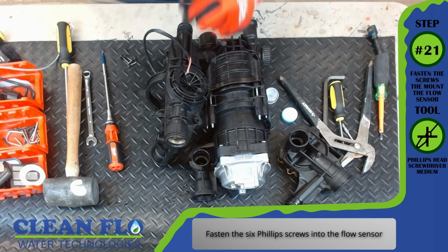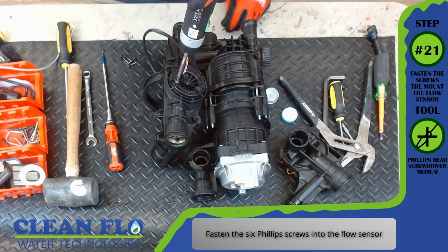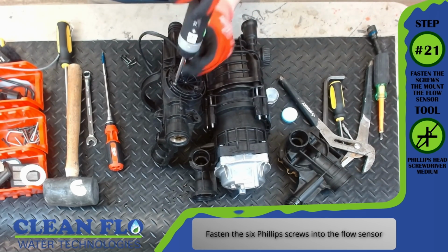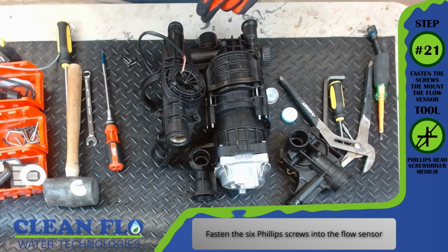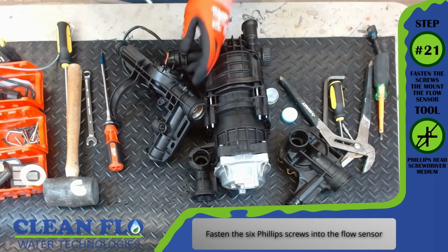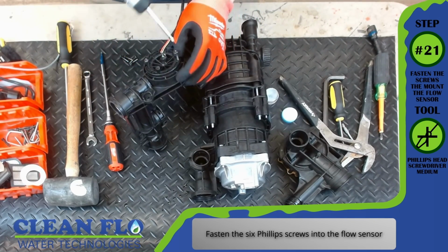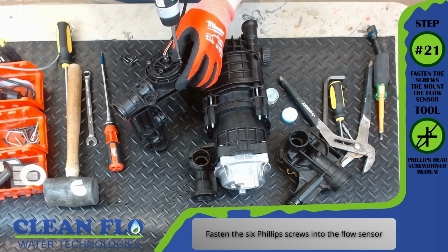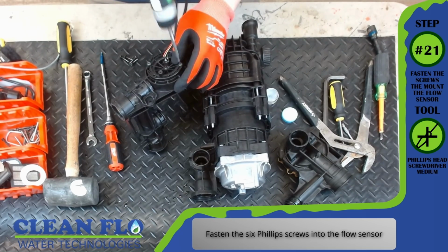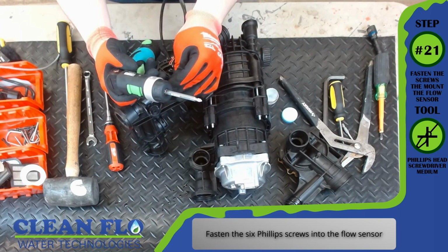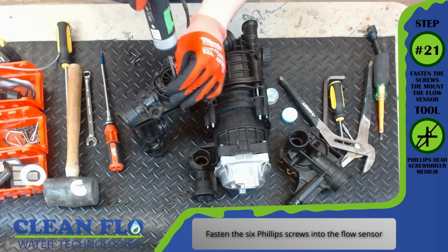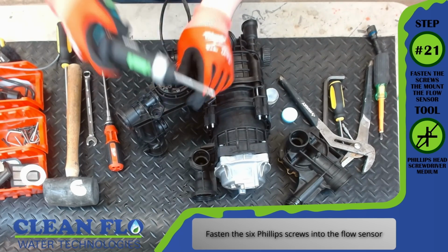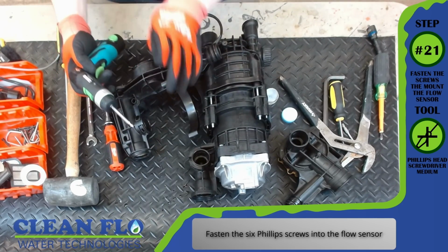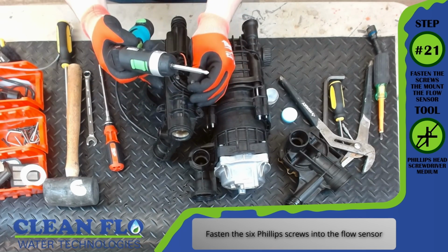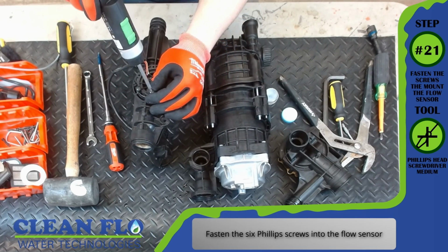Step number 21, fasten the screws that mount the flow sensor. Tool, Phillips head screwdriver, medium. Fasten the 6 Phillips screws into the flow sensor. Even with a flow sensor like this, we will do slight crisscrossing the best we can, so we're not over tightening one side of the flow meter, and we provide even distribution.